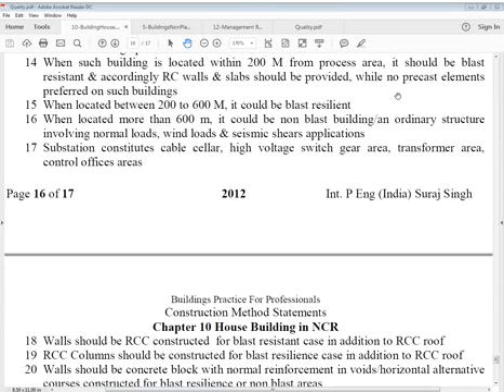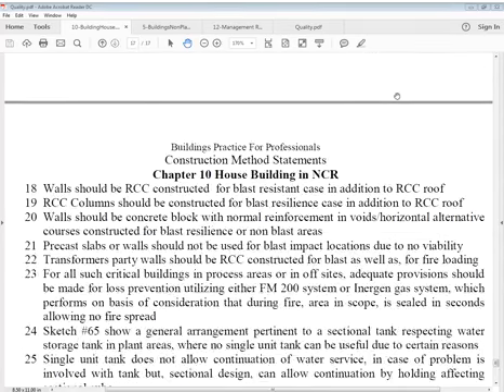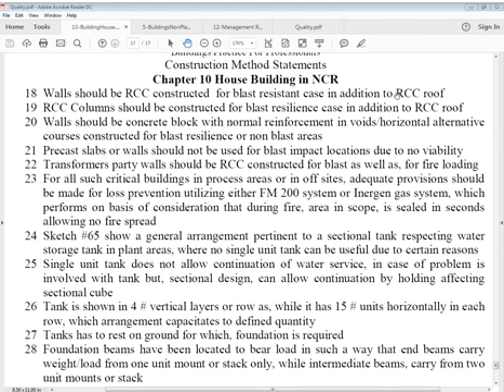When located more than 600 meters away, it could be a non-blast building, an ordinary structure involving normal loads, wind loads, and seismic shear applications. A substation constitutes cable cellar, high voltage switchgear area, transformer area, and control offices area. Walls should be of RCC construction for the blast resistant case, in addition to RCC roof.